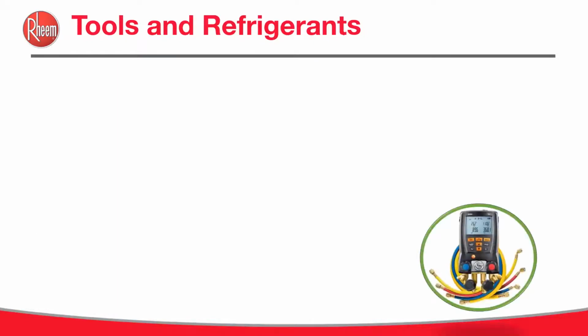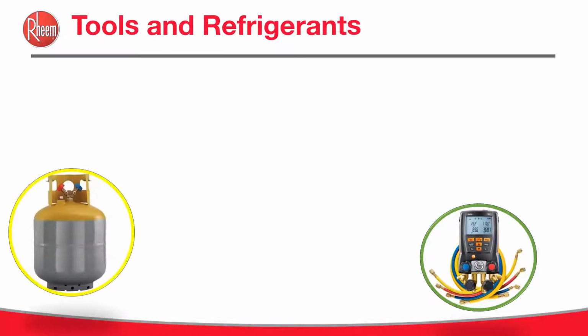So now let's look at tools and refrigerants required. Manifold set, rated for 800 PSIG, properly maintained. There are many brands and varieties available through your local distributor. Recovery cylinders, rated for 400 PSIG. And these are required to reclaim the refrigerants. As we all know, it is illegal to release refrigerant to the atmosphere.